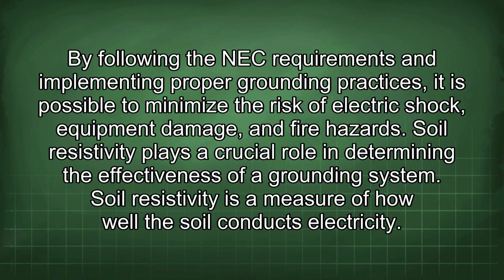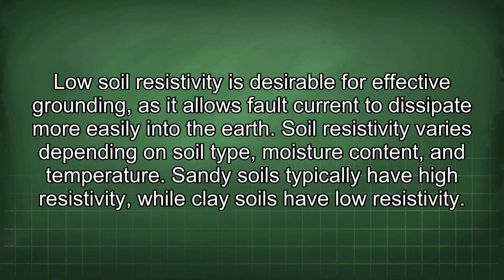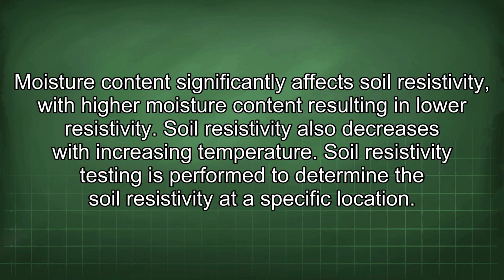Soil resistivity is a measure of how well the soil conducts electricity. Low soil resistivity is desirable for effective grounding, as it allows fault current to dissipate more easily into the earth. Soil resistivity varies depending on soil type, moisture content, and temperature. Sandy soils typically have high resistivity, while clay soils have low resistivity. Moisture content significantly affects soil resistivity, with higher moisture content resulting in lower resistivity. Soil resistivity also decreases with increasing temperature.